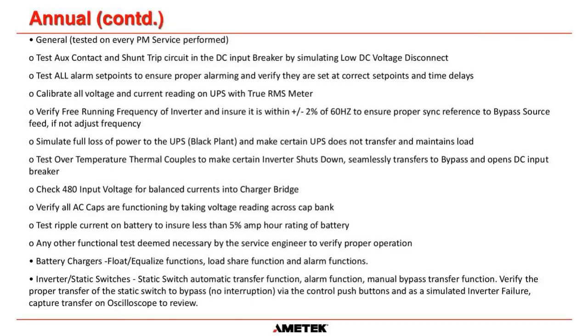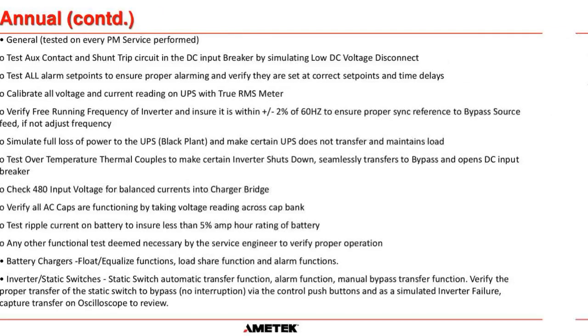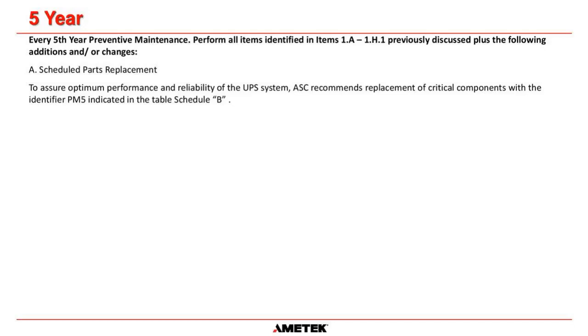And then we simulate a full loss of power to the UPS, a complete plant blackout, AC input and bypass input. We make sure the system runs on batteries. Obviously, you have to have a remote manual bypass switch to do that, but we do that as part of our annual test. We check thermocouples, we check for balanced currents into the charger bridge. That's the biggest indicator of faulty SCRs in your rectifier, is if the input currents are unbalanced. We verify all the AC caps are good. We test the ripple current, go into the battery and make sure it's less than 5% of the ampere hour rating of the battery. And then we test charger float equalize functions, and we check operation of the inverter static switch. So you can see the annual checks that we do are actually very, very in-depth.